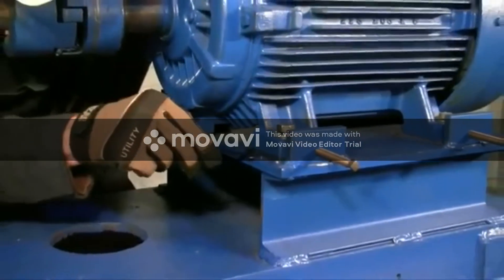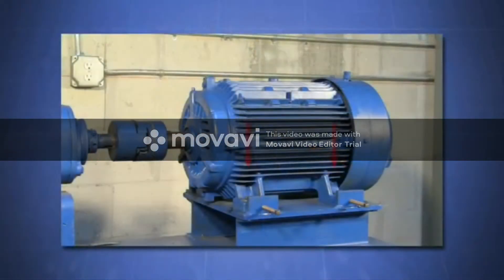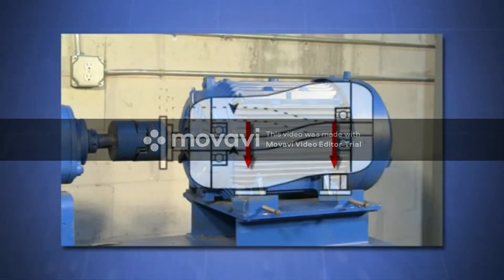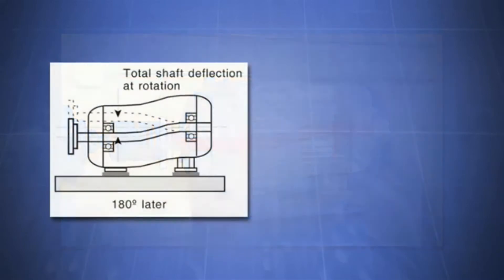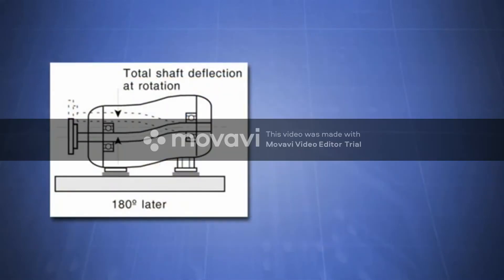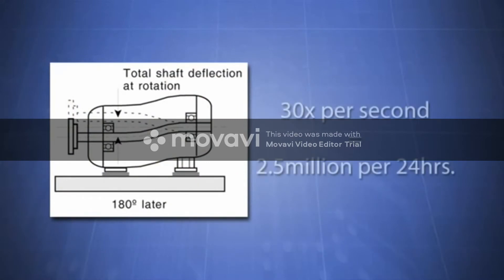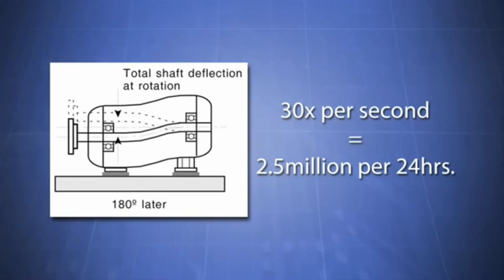Machines are built out of many parts machined within close tolerances. The distortion of a machine from soft foot causes all those precision machined parts to move out of alignment. Soft foot also causes shaft deflection. A typical machine running at 1800 RPM with a soft foot condition could force the shaft to bend back and forth 30 times a second, or two and a half million times every 24 hours. Think about what this increased vibration would do to the reliability of your machine.